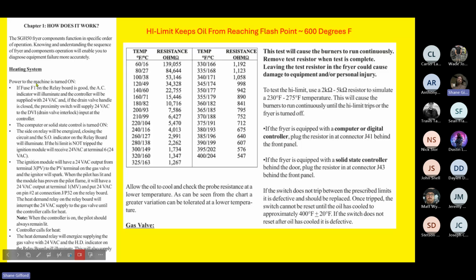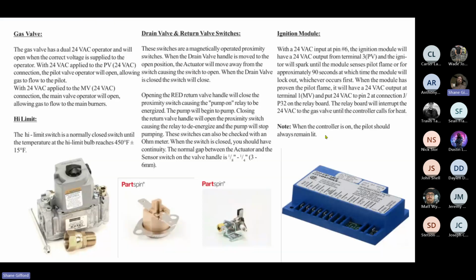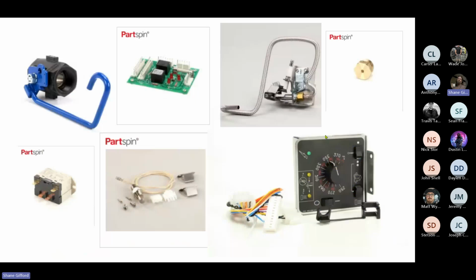So this one's saying, power to the machine is on. If fuse F1 on the relay board is good, the AC indicator will illuminate and the controller will be supplied with 24 volts VAC. And if the drain valve handle is closed, the proximity switch will supply 24 to the drain valve interlock input at the controller. So I'm going to see if I can hop back and forth. As you might see on the Pitco fryers, there's your drain valve right there. There's one of the control boards, the pump relay.